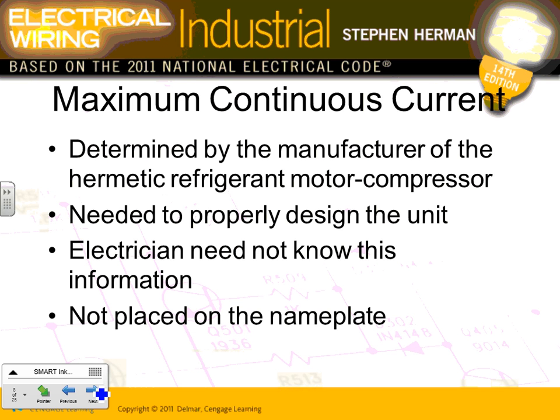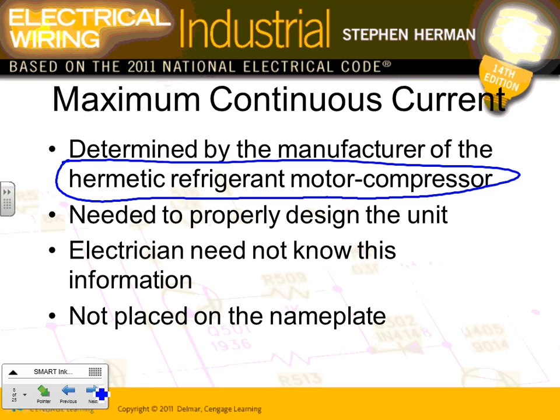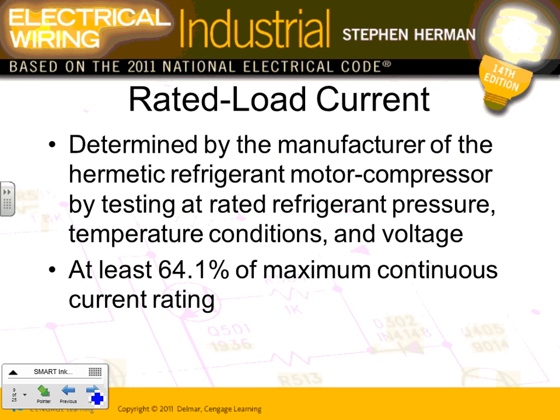Okay, a few things, guys, about the maximum continuous current rated by the manufacturers of what they call the hermetic refrigerant compressor motor. That's done by the manufacturer, needs to be properly designed for the unit, not done by us. We don't care too much about it. It's not on the nameplate, so this is just FYI only. The second one, the rated load amps, Jeff, is the most important one. You have to put the rated load amps on the nameplate.